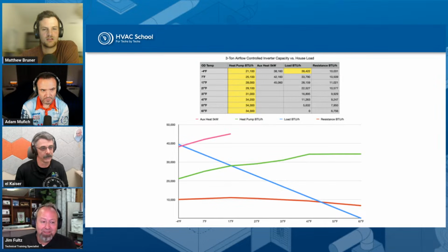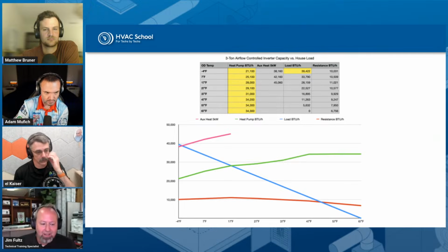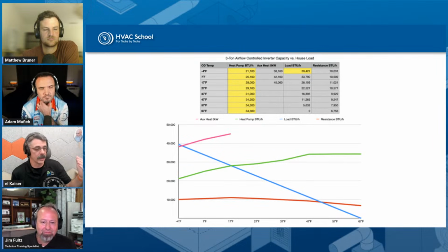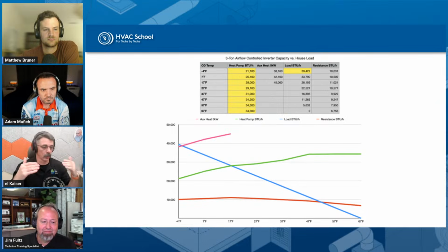Mm-hmm. Right. So when you have a consistent temperature, like an open loop or a ground source, basically what you're saying is, if you're looking at any of these charts, the COP fluctuates drastically based on outdoor air temperature. But if you have one of these types of systems that we're just talking about, the COP stays in a much tighter range. Absolutely. Because in that case, your evaporator coil or outdoor coil, your heat source coil, is not really ever changing temperature drastically. You wouldn't see this green line fall off very much. Right, it'd pretty much be a flat line. That water temperature might be consistently up at 57 degrees, so you're always going to have that 35,000, 36,000 worth of heat there, unless that water temperature starts falling.